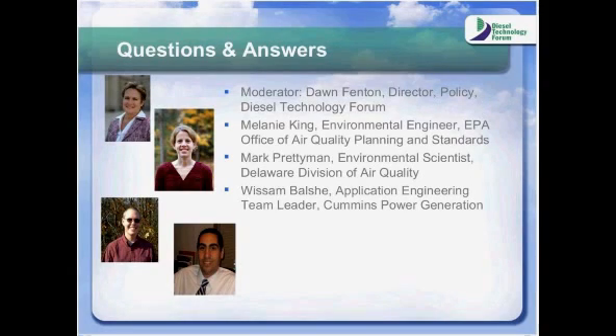Yes. Well, there isn't a rule of thumb that you can apply. It really depends on the engine and the size of the engine. You should consult with the genset and engine manufacturer for that, but I can tell you that the rule of thumb is to keep a minimum of 30% load on the engine. If you keep a minimum of 30% average load on the engine, that will basically reach the desired temperature for the exhaust to prevent wet stacking and carboning.